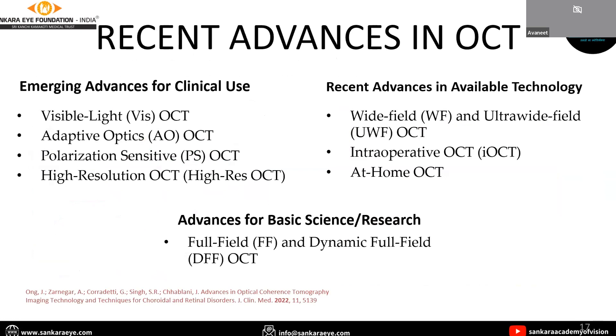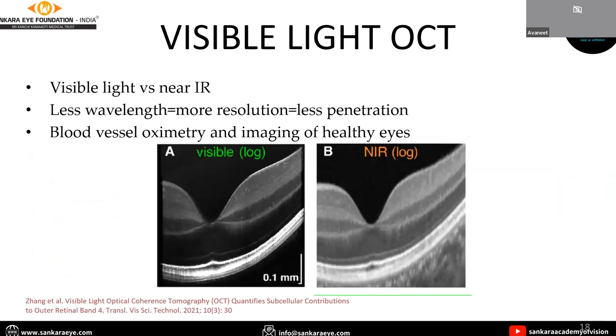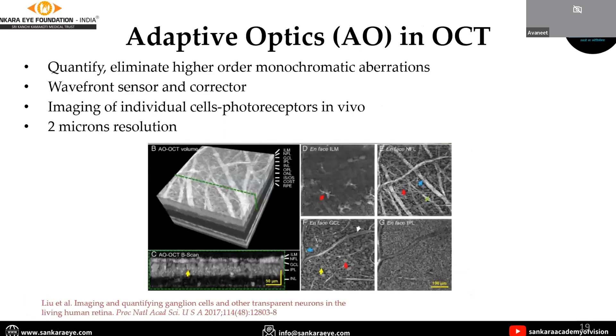Coming to recent advances in OCT, with changes in optics we can have different benefits. Visible light can be used instead of near infrared light — because of the shorter wavelength, resolution will improve. We can see the difference between images using visible light versus near infrared light. Adaptive optics in OCT can quantify and eliminate higher order monochromatic aberrations using wavefront sensors and correctors, achieving a resolution up to two microns.